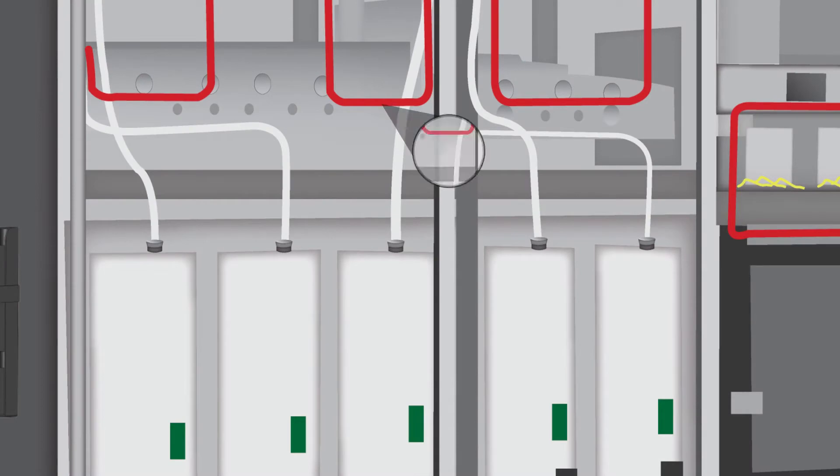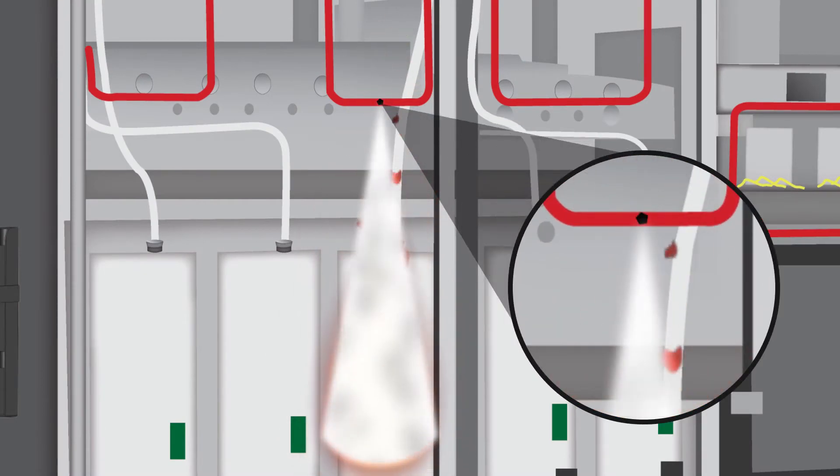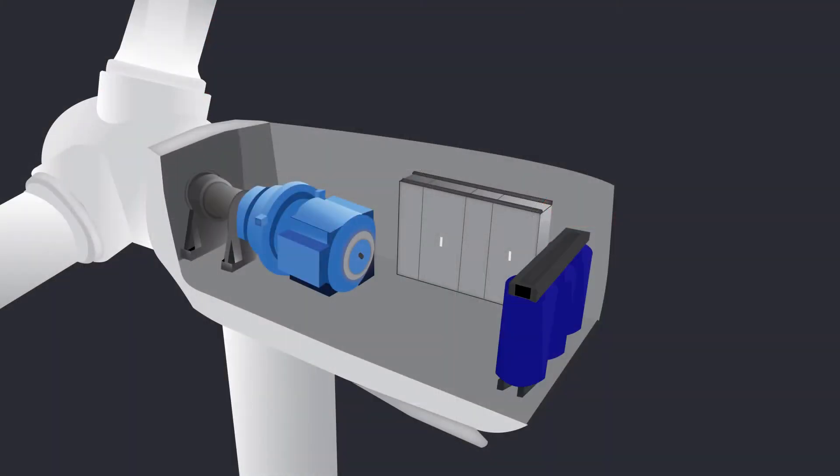The direct release system delivers the suppression agent through the burst hole and is ideal for the turbine's enclosed environments like the control panels and capacitor cabinets.